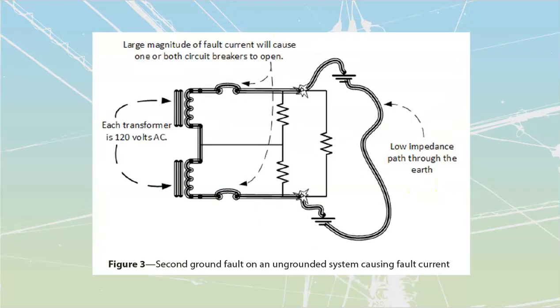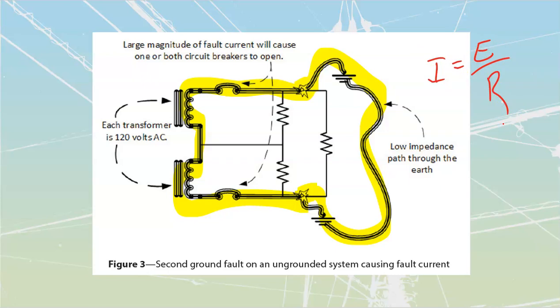What we would have to wait for is a second fault, that one over there, that would then complete this path. And at that point, we're going to have a complete path for current flow through our transformers. And because the path itself is going to be low impedance, I is equal to E over R, we would get a fairly large amount of current that's going to flow, right? 240 volts over, let's say, 2 ohms of resistance over there. So we'd have like 120 amps. Should be enough that it's going to kick out one, if not both, of these instantaneously. Well, close to instantaneous. Depends on the response curve.